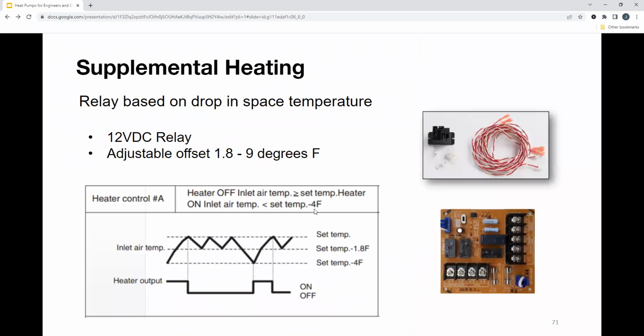And then supplemental heating, if you wanted to use heat pumps as the first stage, you could do so. And then you could add this 12 VDC relay that can adjust between 1.8 and 9 degrees. What that does is it connects to every fan coil unit and basically operates based on drop in space temperature. The default setting is typically 4 degrees. So in the case where it's wintertime, we're trying to set it to 70 degrees, the VRF system can't keep up, or someone opens up a window, right, and that temperature drops to 66. What's going to happen is this relay will kick on any third-party supplemental heating until it brings it back up to set point, and then it will shut off accordingly.